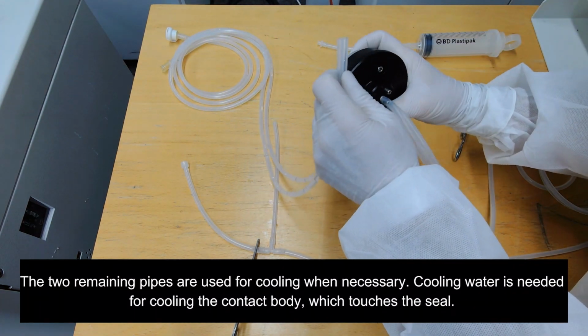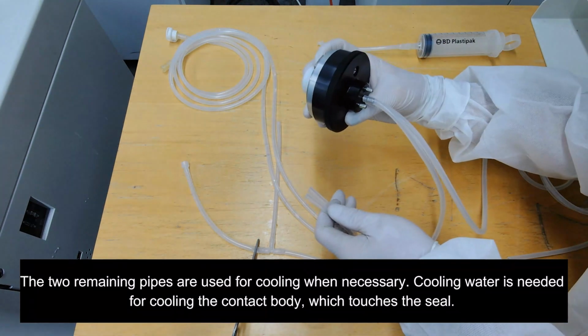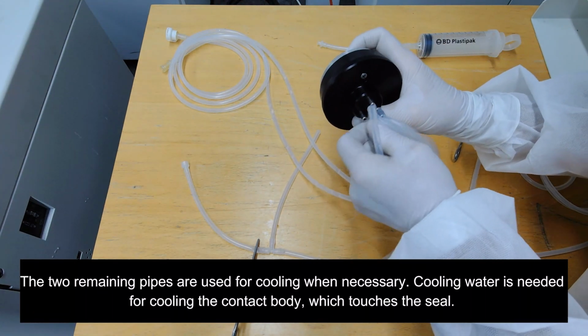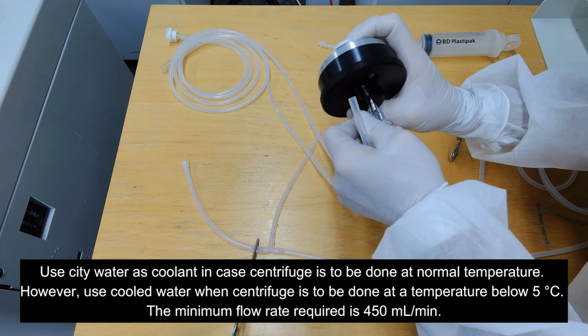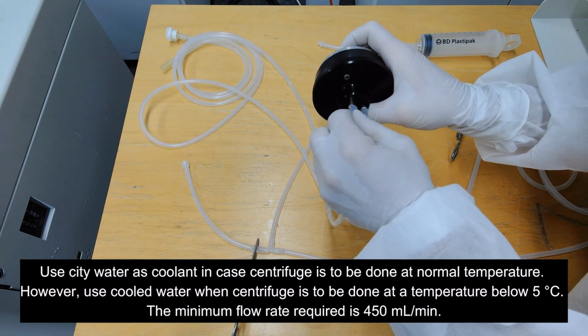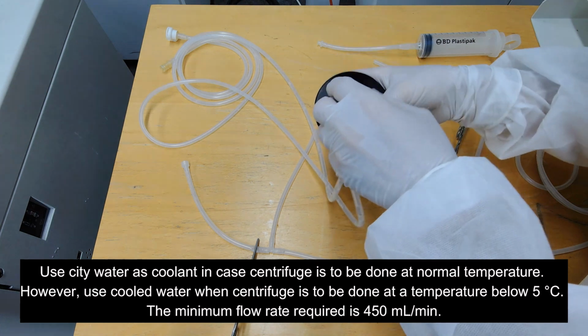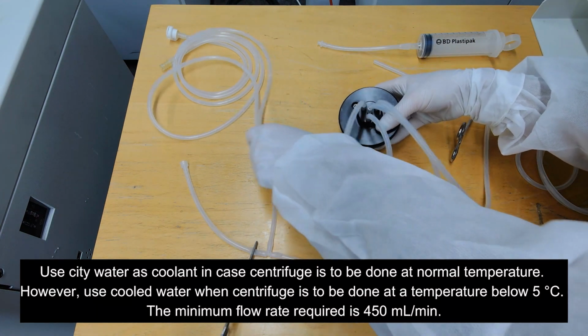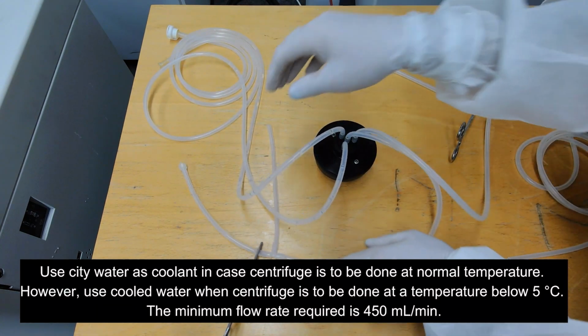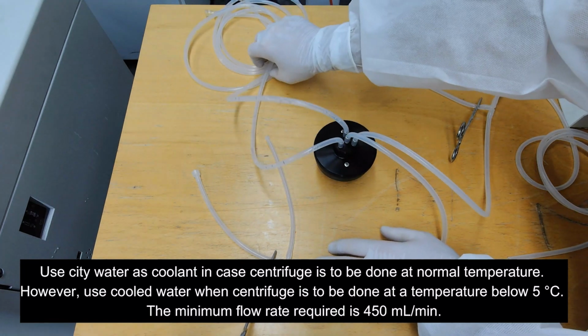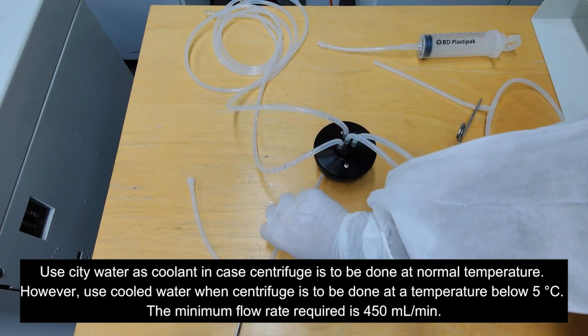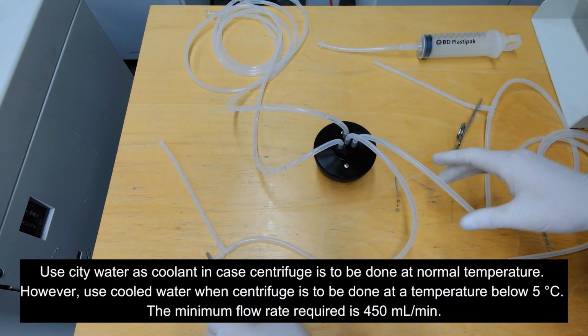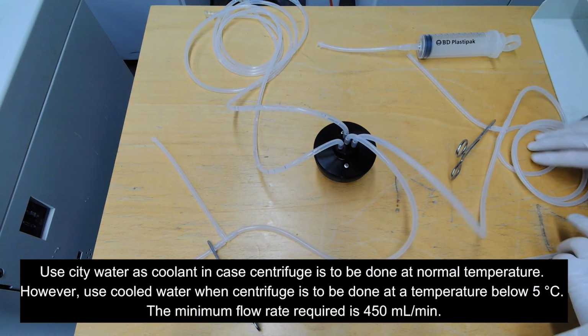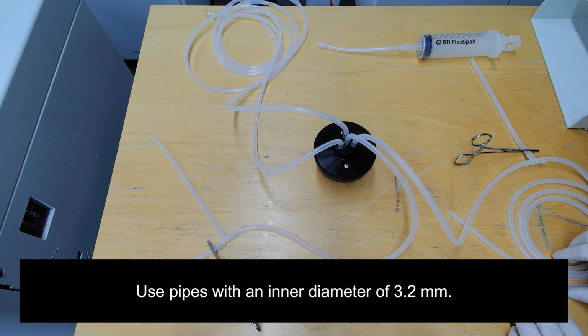Cooling water is needed for cooling the contact body which touches the seal. Use city water as coolant in case centrifugation is to be done at normal temperature. However, use cold water when centrifugation is to be done at temperature below 5 degrees C. The minimum flow rate required is 450 ml per minute. Use pipes with an inner diameter of 3.2 mm.